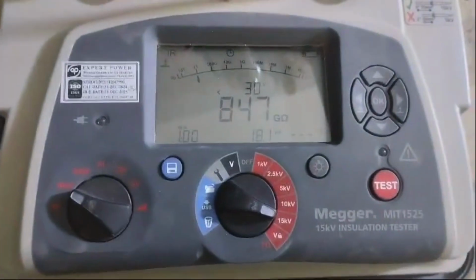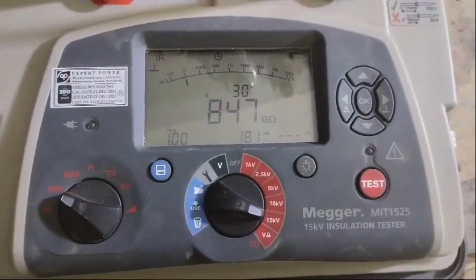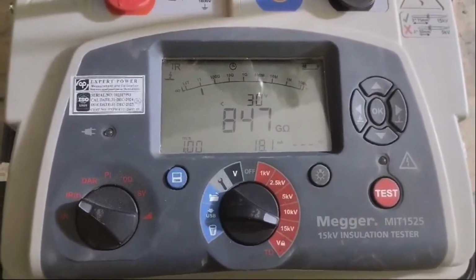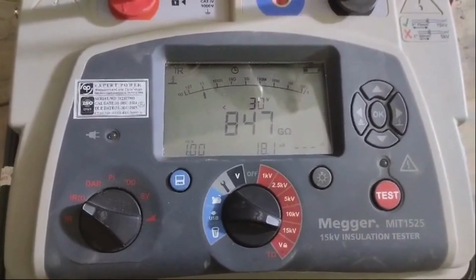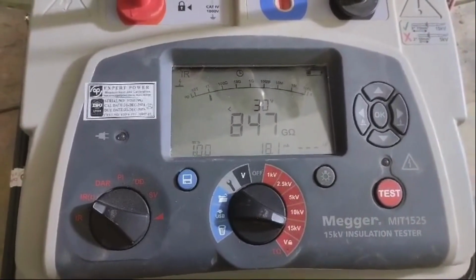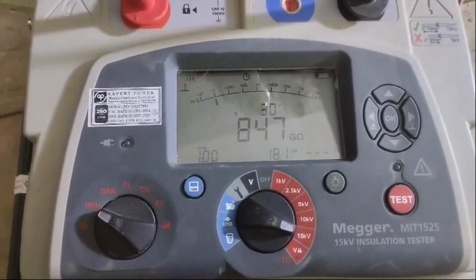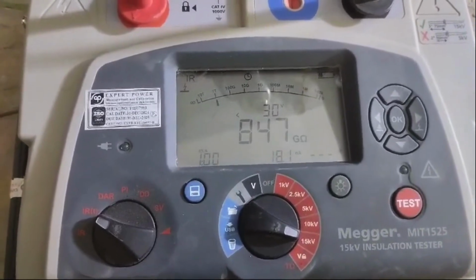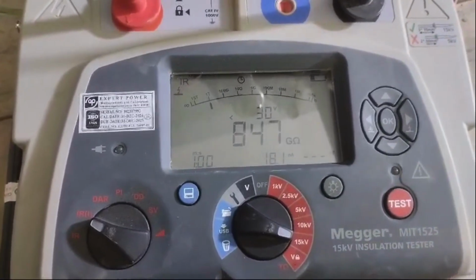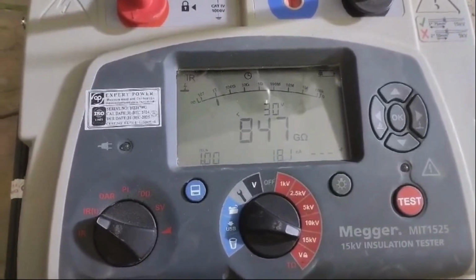Now we are taking the readings. We are injecting 15 kilovolt for this 33 kV high voltage switchgear cable. For low voltage we mostly inject 1 kilovolt, but for high voltage we are injecting 5 kilovolt DC supply.